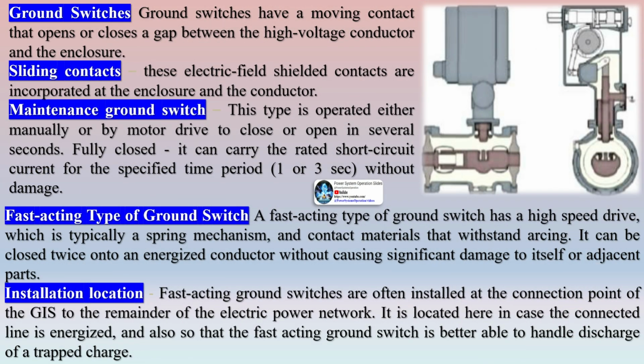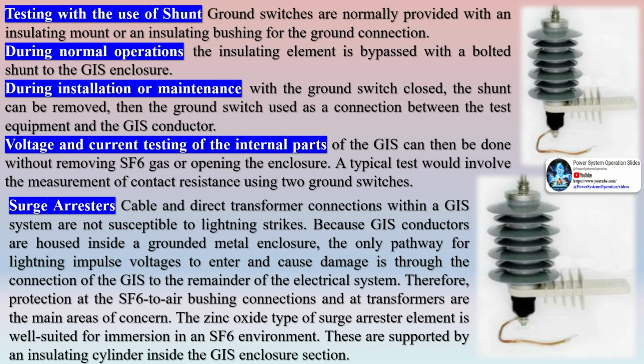Ground switches have a moving contact that opens or closes a gap between the high voltage conductor and the enclosure. Sliding contacts. These electric field shielded contacts are incorporated at the enclosure and the conductor. Maintenance ground switch. This type is operated either manually or by motor drive to close or open in several seconds. Fully closed, it can carry the rated short circuit current for the specified time period, 1 or 3 seconds, without damage. Testing with the use of shunt ground switches: these are normally provided with an insulating mount or an insulating bushing for the ground connection. During normal operations, the insulating element is bypassed with a bolted shunt to the GIS enclosure.